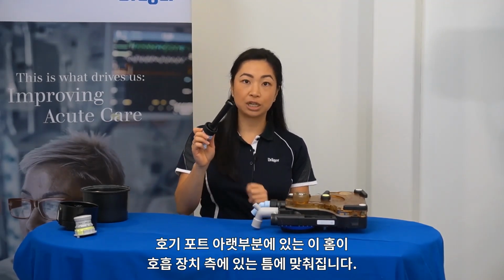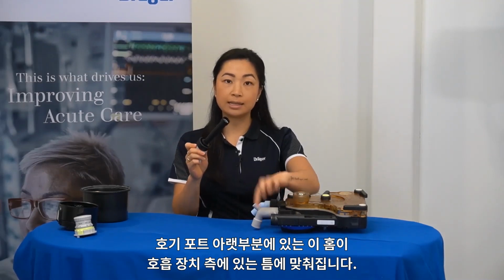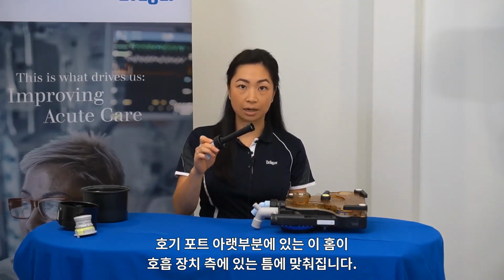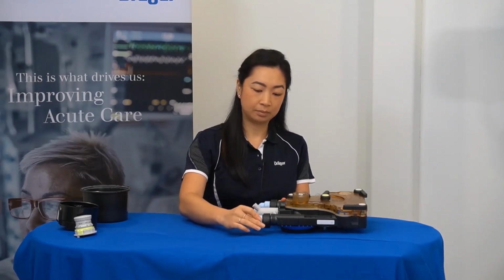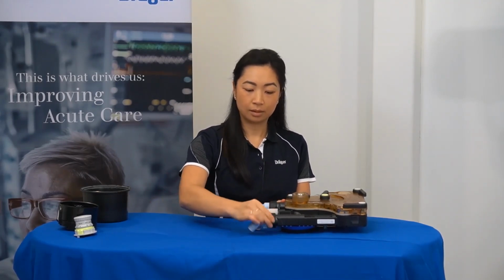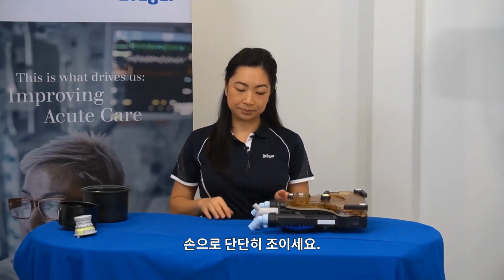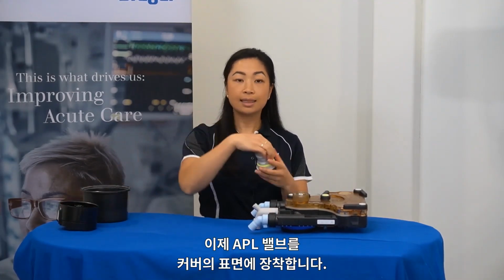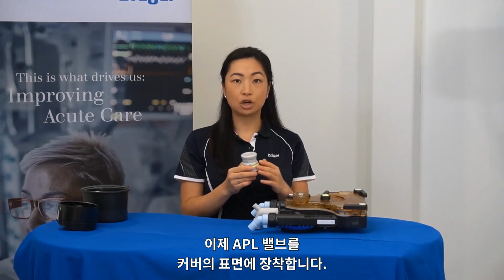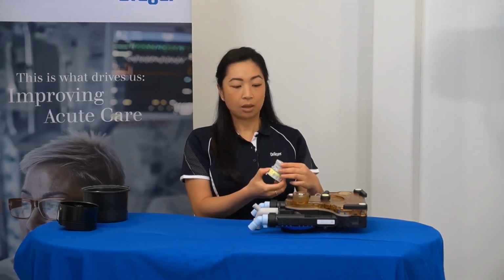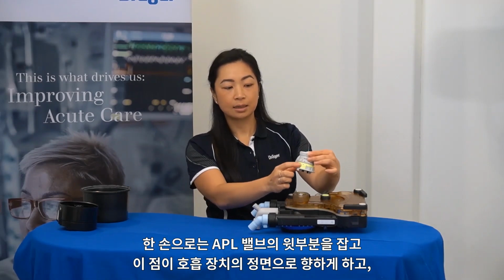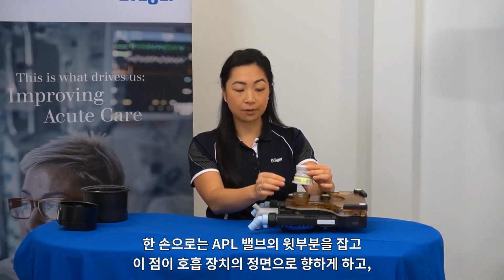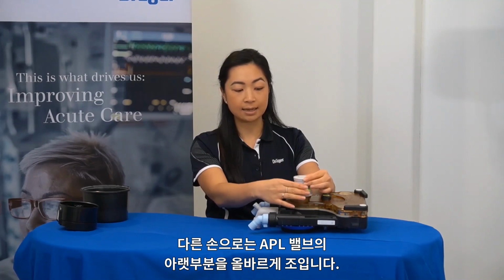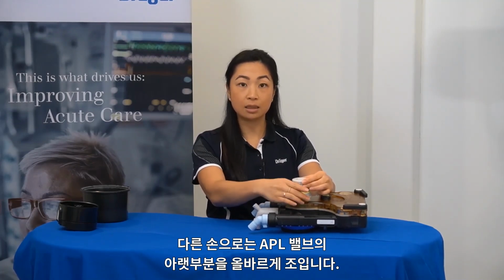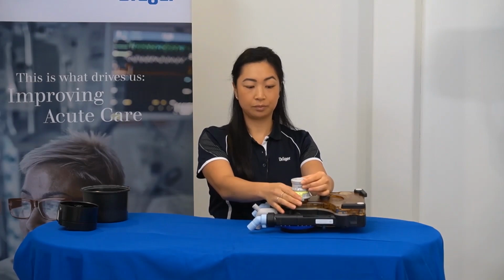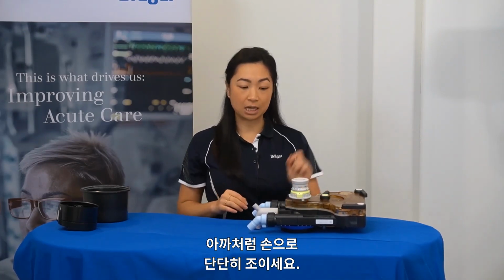Remembering there is a notch at the base of the port that aligns with the gap in the side of the breathing system. Ensuring it is finger tight. Then the APL valve can be placed on the top of the cover. With one hand, aim the dot to the front of the breathing system, and with the second hand, correctly threading the base of the APL valve. Once again, just so it's finger tight.